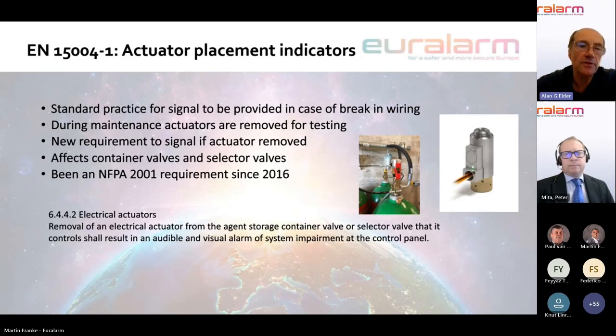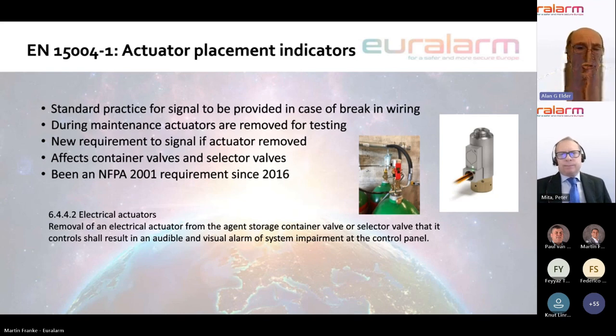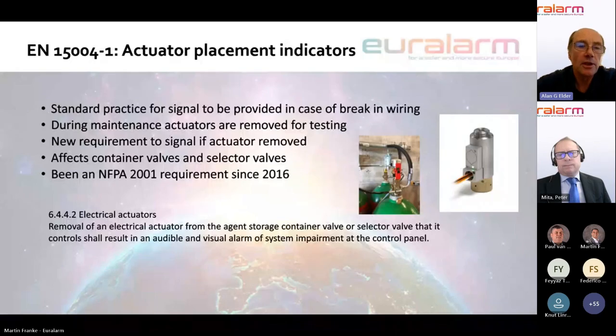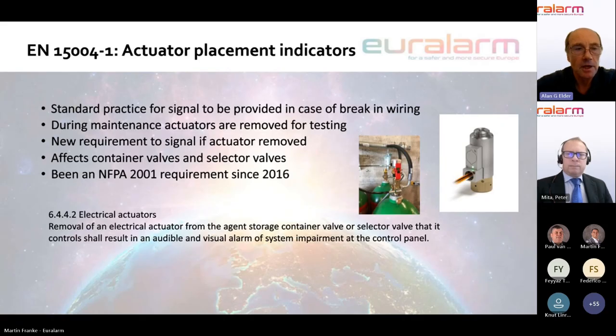Now, during the maintenance activities of systems, which normally takes place at least every 6 months, the actuators are removed for testing. That does not necessarily include disconnecting the electrical wiring. And there have been anecdotal reports that during maintenance activities where the actuators have been removed, they have not been replaced following the maintenance work. That would render the system ineffective and incapable of discharge. So what has been introduced in this version of the standard is a requirement to provide a signal if the actuator is removed mechanically from the container valve or from the selector valves it controls. So what we've now got is the requirement to provide a signal in the case of a break in the wiring, a break in electrical continuity, or if the actuator itself is removed from the cylinder valve.